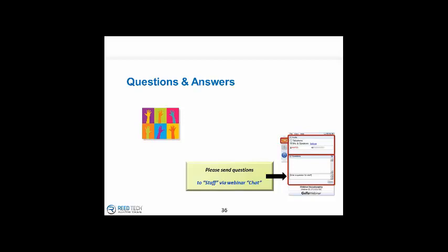Okay. Other topics. First, a couple of people left and said, thank you, great presentation, very informative. Marilyn asks, is it possible to do your submission in phases? We have hundreds of products, and Marilyn, you have my sympathy. The answer to that is yes. As you have individual products where the full record is complete, you will have to submit complete records to the FDA, but you can take your inventory of 10,000 and just work on a product family initially and piecemeal it out one at a time, or groups of 10 or 1,000, whatever is most convenient.